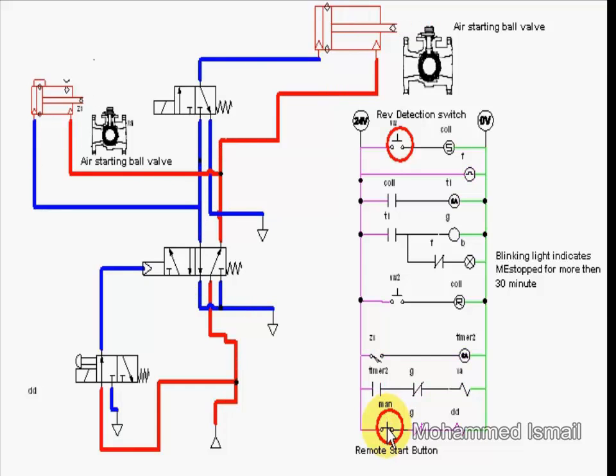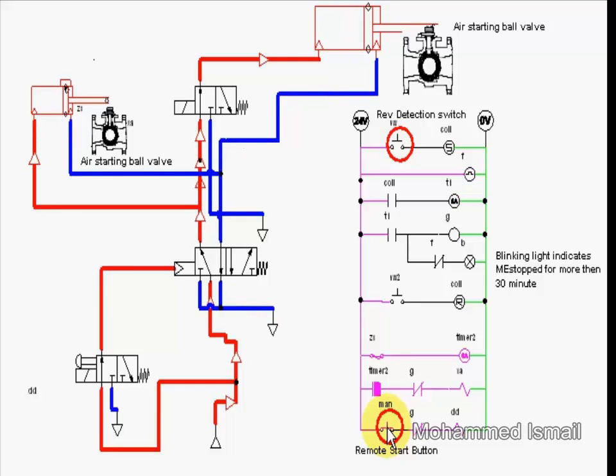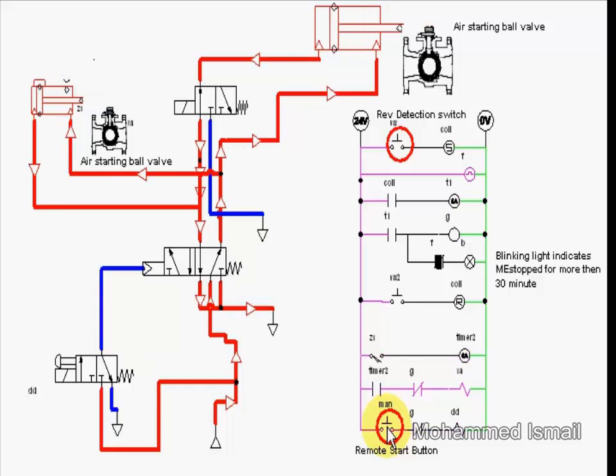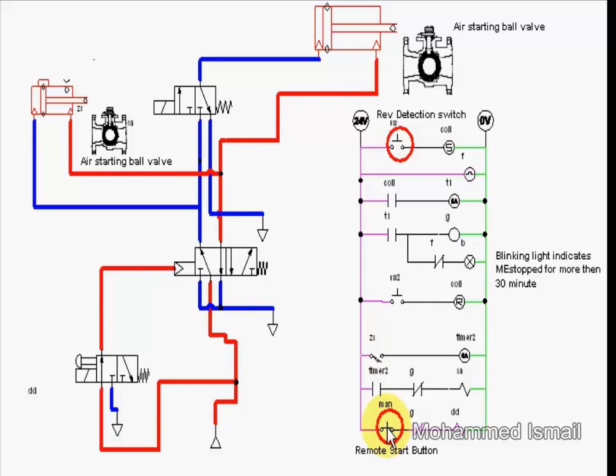The above figure shows the pneumatic and electrical control implemented to achieve the slow turning sequence. The sequence is achieved by pneumatic directional valve, solenoid valve, timer, and revolution detector.